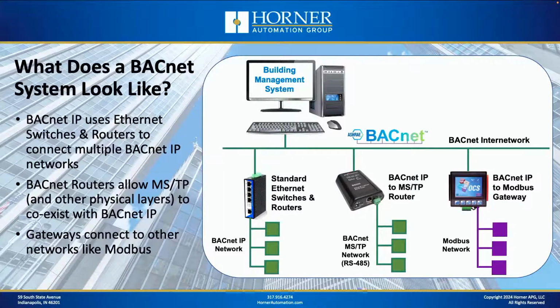You could have a whole bunch of these different separate networks that are all interconnected, so that on a building management level, maybe at a campus level, there can be literally thousands and thousands of devices that are all tied on the same system. And it can be a combination of devices that are sitting directly on a BACnet over Ethernet network connected to standard Ethernet switches and routers.